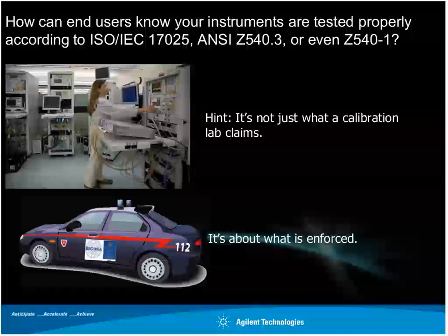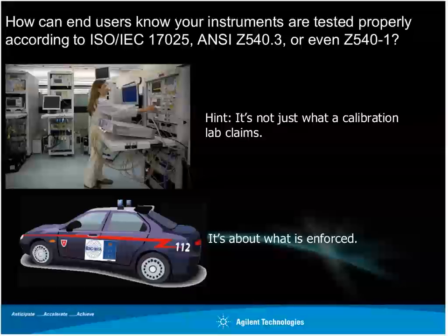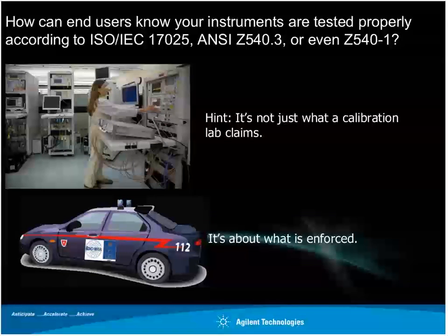Oftentimes, if they're accredited, then really, and so here you have, Trevor probably wishes he had a car this fancy, but it's really, and I know that sometimes the accreditation bodies are sensitive to the word enforced, but really as they're doing that assessing function of a calibration laboratory, calibration is really about trust. And you can have more trust in a laboratory if you know that a qualified third party who really understands those calibration standards, like UKAS, has done a thorough assessment of them and has posted that on their website.